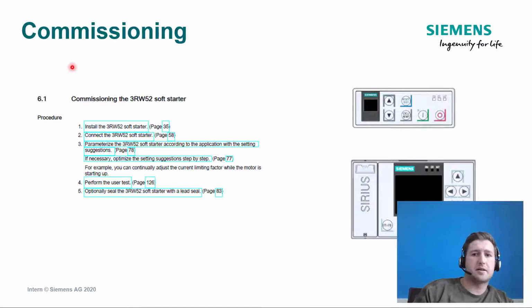So how do you commission and how do you parameterize the device? My main tip is you'll install the device as we just looked at on the previous slide, and connect the device as we discussed on the previous slide, and then you need to parameterize the potentiometers.